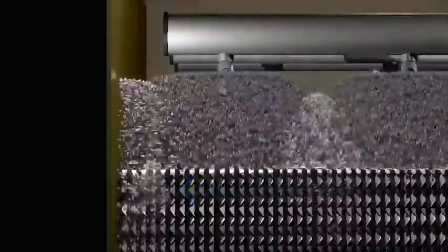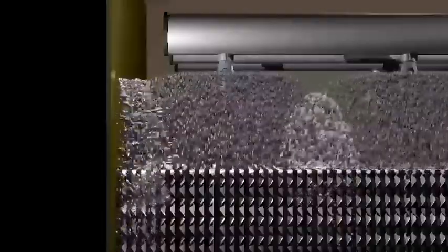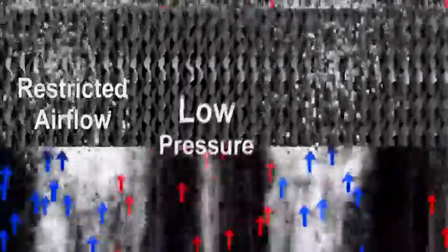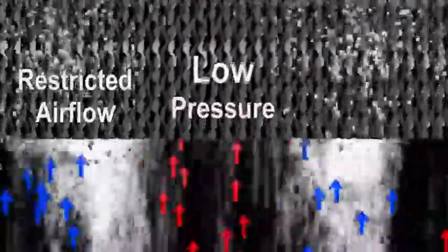So what's so bad about wall water? It had to be pumped to the top of the cooling tower. It flows down through the flooded areas of the film media, mixing with little to no airflow, and as a result, receiving poor heat transfer. As with the nozzle overlaps, the airflow in this area is restricted and is directed into the adjacent film media with less pressure. Another gross waste of both pump and air energy.